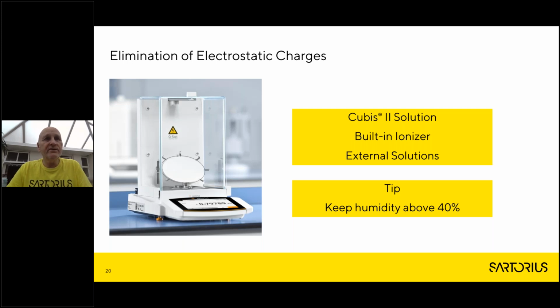Now, on opening the draft shield, the ionizer can be set to automatically activate for a length of time, and this will discharge any charges on our sample or tare vessel. And then when we close the draft shield, we should have no influence and no effect on our weighing process. Static appears typically at a very low humidity. So if you can keep your humidity above 35 to 40% in the laboratory, you will have less effect of static influence.